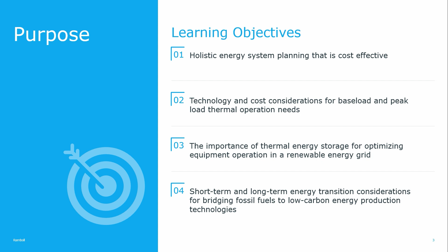We'll talk about planning from a holistic standpoint, baseload peaking, the role of thermal energy storage, and making sure we've got enough electrical capacity. If we learned anything from the SUNY work on the campuses, and we did 8 of those over the last 18 months, it's that some of them were in really good shape and had capacity, but if you were going to full electrification, they didn't have the capacity. So you either need to upgrade at the campus level or upgrade at the utility level. And then we'll cover some project examples.